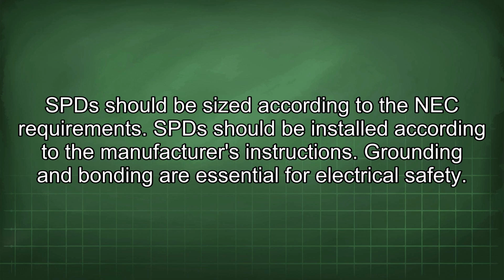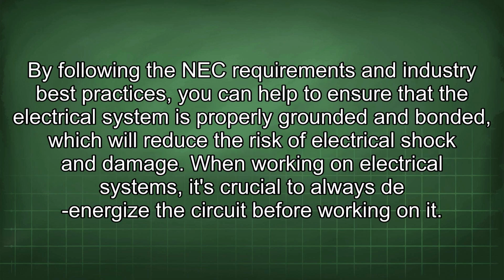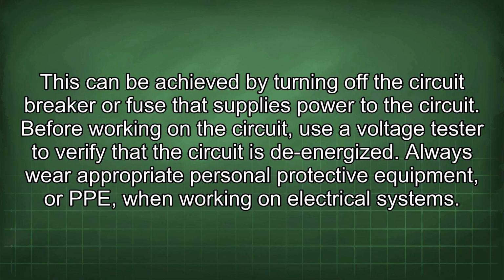Grounding and bonding are essential for electrical safety. By following the NEC requirements and industry best practices, you can help to ensure that the electrical system is properly grounded and bonded, which will reduce the risk of electrical shock and damage. When working on electrical systems, it's crucial to always de-energize the circuit before working on it. This can be achieved by turning off the circuit breaker or fuse that supplies power to the circuit. Before working on the circuit, use a voltage tester to verify that the circuit is de-energized.